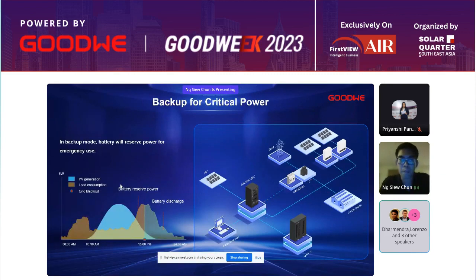Last but not least, backup mode. Besides grid operation, our battery energy storage systems also support backup function during power outages. We are very proud to announce that we are able to do UPS-level switching, meaning during a power outage our battery system will switch into backup mode in 10 milliseconds. We can charge our batteries during peak hours or excess power, and even have capacity reserved so that during an outage it can discharge and support local loads. This gives 24/7 power supply even during grid backup.